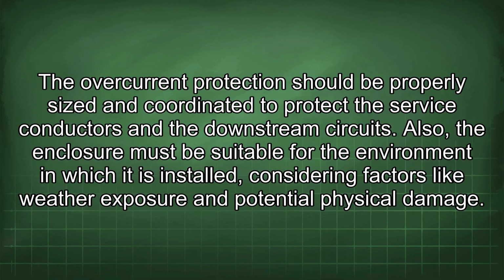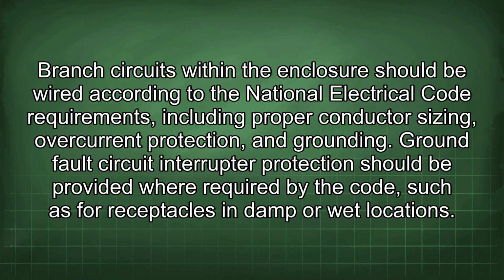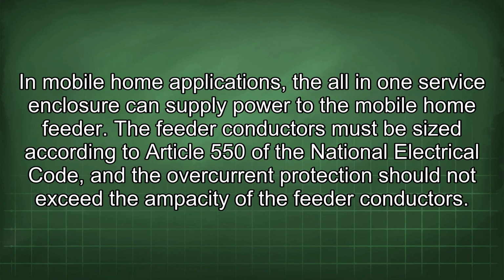Also, the enclosure must be suitable for the environment in which it is installed, considering factors like weather exposure and potential physical damage. Branch circuits within the enclosure should be wired according to the National Electrical Code requirements, including proper conductor sizing, overcurrent protection, and grounding. Ground fault circuit interrupter protection should be provided where required by the code, such as for receptacles in damp or wet locations. In mobile home applications, the all-in-one service enclosure can supply power to the mobile home feeder.